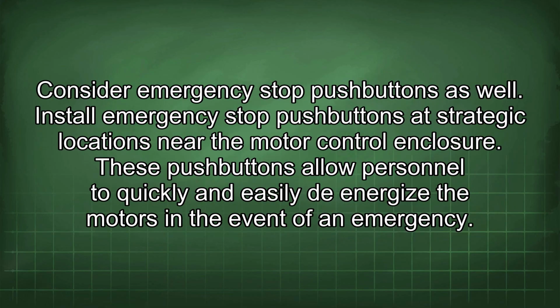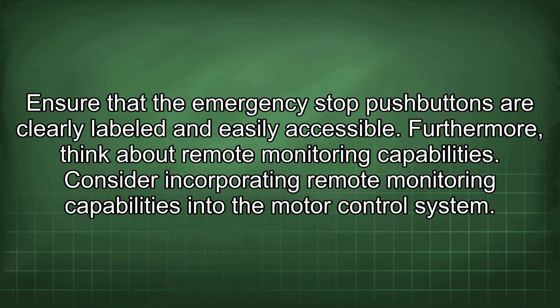Consider emergency stop push buttons as well. Install emergency stop push buttons at strategic locations near the motor control enclosure. These push buttons allow personnel to quickly and easily de-energize the motors in the event of an emergency. Ensure that the emergency stop push buttons are clearly labeled and easily accessible.